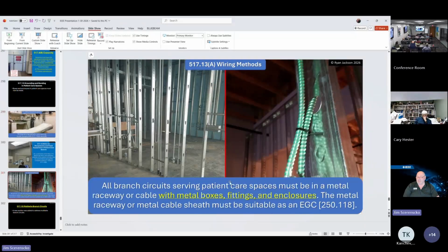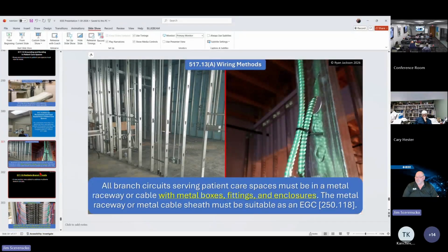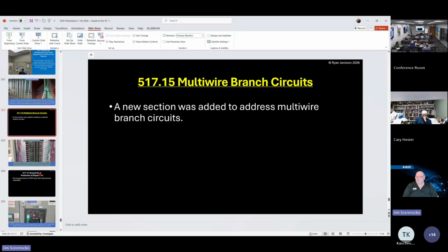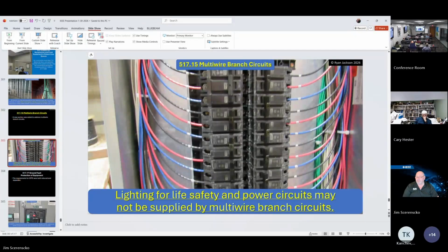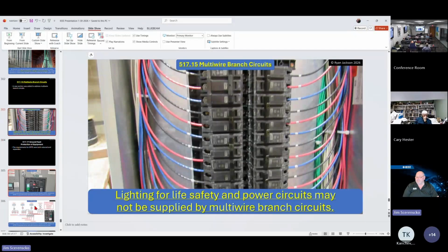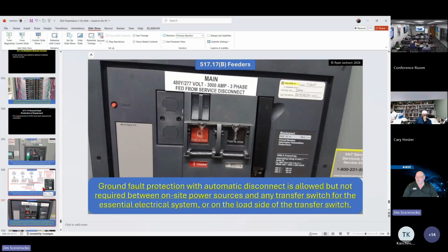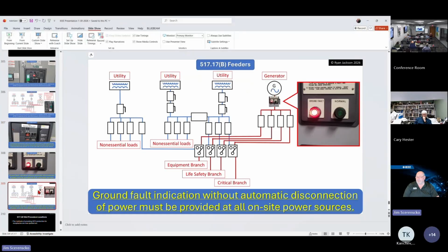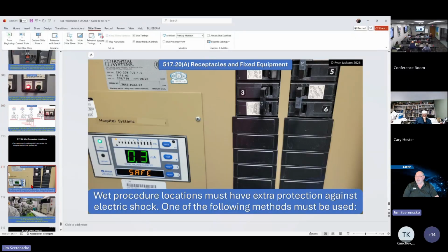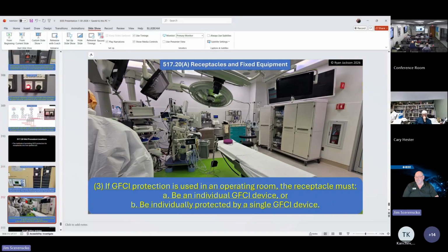which is also, you know, what we call hospital grade MC cable, what we also say is a redundant ground, to make sure that it's used with metal boxes, metal enclosures, multi-wire branch circuits and the use of them. Not allowed on life safety and power circuit equipments in patient care areas. The ground fault protection for the disconnecting means is allowed but not required between on-site power sources and transfer switches for the essential power systems. Some other change, a lot of changes in the essential power systems.